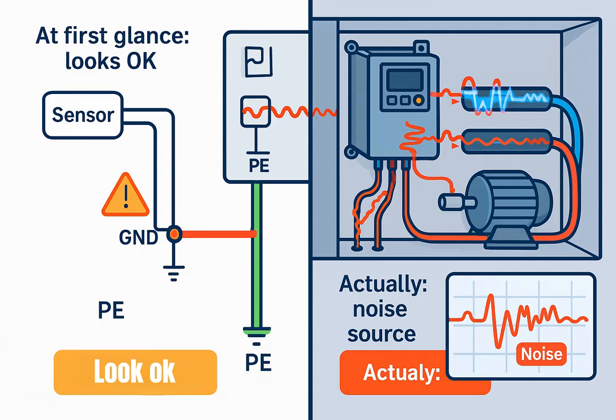PE, protective earth, is mainly for safety, not for measurement. It is used to carry fault current, leakage current, surge, high-frequency noise. It is not guaranteed clean enough to be a reference for small analog signals. When you use PE as your signal reference, you force your analog sensor to share the same path with noise from VFDs, leakage from motor frames, switching noise from contactors and soft starters.